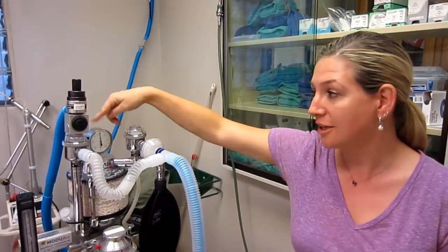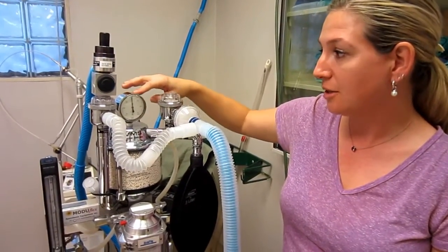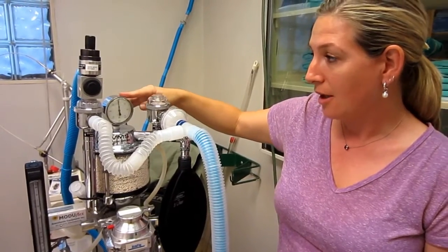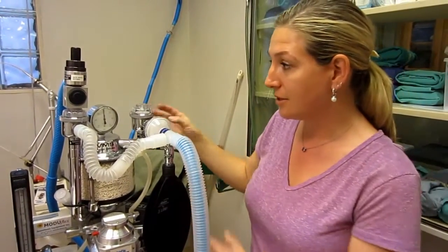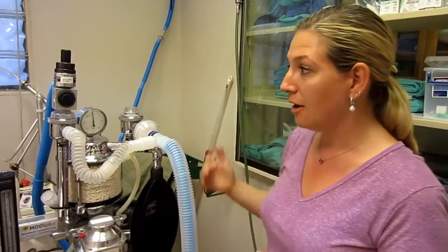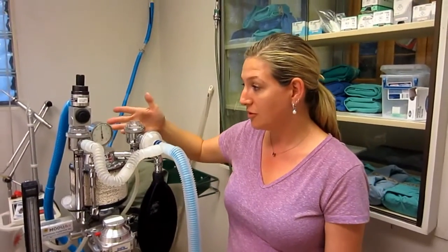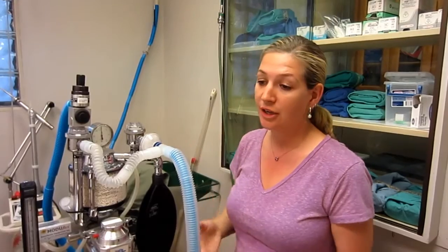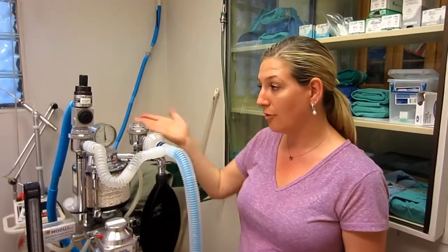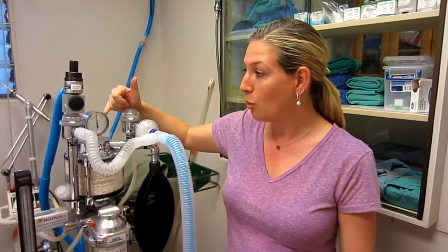So one thing I didn't mention is the manometer. What this does is it actually shows us the pressure of the system. So this should stay, when we're doing spontaneous breathing, it will actually register somewhere between 0 and 2. This is useful for that, but it's also useful during our pressure check. I'm going to be referencing the manometer again, and we're going to have it up to 20 for our pressure check of cm of water or H2O.